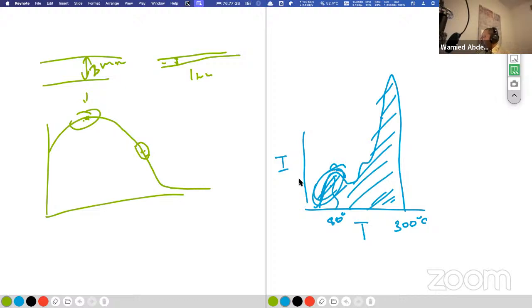So a proper way to do dosimetry with TLDs is you need to have some discipline. When you calibrate the TLDs, for example, you shoot them at 3 o'clock or the end of the day, then you wait until the next day, let's say 12 hours, and then you read the TLD. We know the dose that we delivered to the TLD, and the reading is based on this light intensity, so we can get a calibration factor for the TLD.